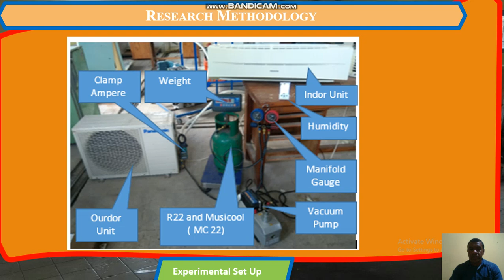Now this is the experimental setup. Clamp ampere is to know how much current is consumed in this research. Weight is to know how much refrigerant is used, and there are the indoor unit and the outdoor unit. This is the R22 and Musicool or MC22, and a humidity tool, which is used to measure the humidity of the air in this room, and a manifold gauge to know the pressure when the system is working, and a vacuum pump to vacuum the system. After we vacuum, we charge the system to know the performance of this AC system.